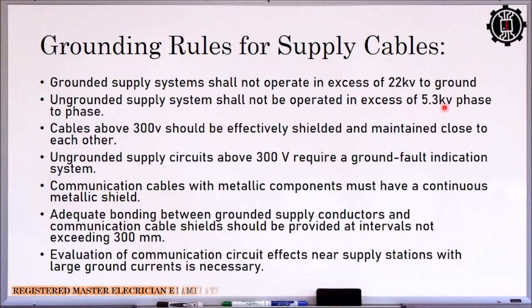So cable above 300 volts should be effectively shielded and maintained close to each other. Ungrounded supply circuits above 300 volts will require a ground fault indication system. Communication cables with metallic components must have a continuous metallic shield. Then adequate bonding between grounded supply conductors and communication cable shields should be provided at intervals not exceeding 300 mm. Then evaluation of communication circuit effects near a supply station with large ground currents is necessary. So this is done so that we know what the ground fault current is. That is to minimize interference, in case our communication circuit is passing near our supply cable.